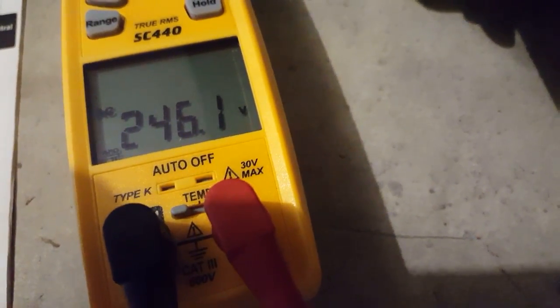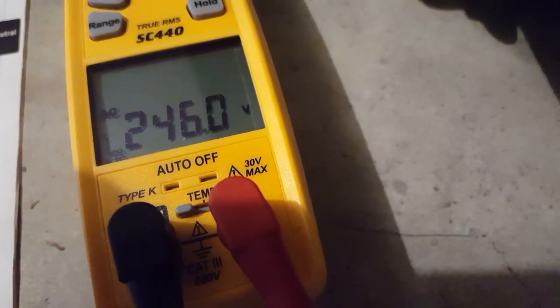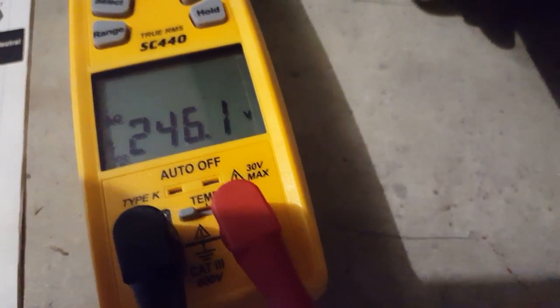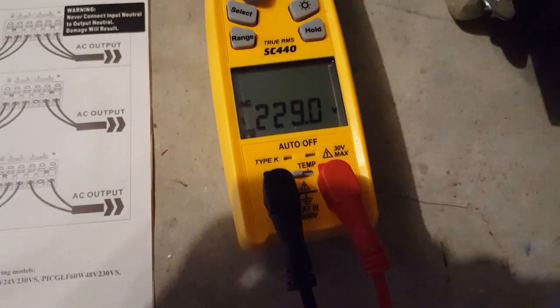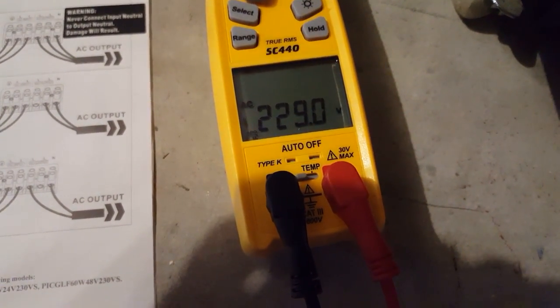So we're going to check the voltage on this red wire and black wire. We should have 246.1. There he is, 246, almost 246.1, it goes up and down. If I unplug that right there, I'm going to do that. Unplugged it, the lights went dim, and now we're at 229.1 volts.